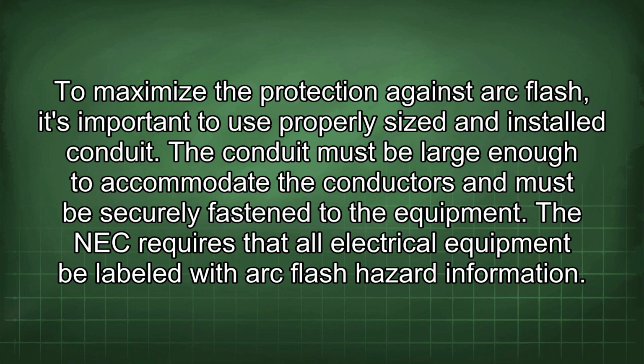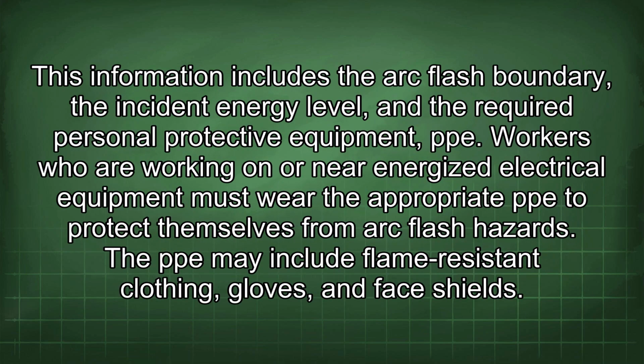The NEC requires that all electrical equipment be labeled with arc flash hazard information. This information includes the arc flash boundary, the incident energy level, and the required personal protective equipment, PPE. Workers who are working on or near energized electrical equipment must wear the appropriate PPE to protect themselves from arc flash hazards. The PPE may include flame-resistant clothing, gloves, and face shields.